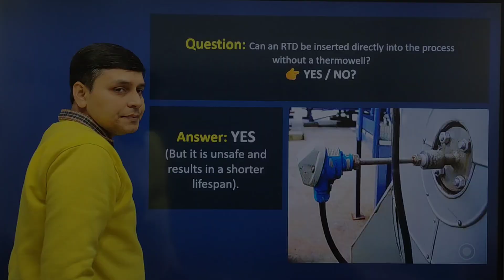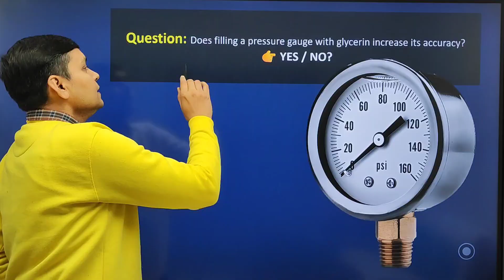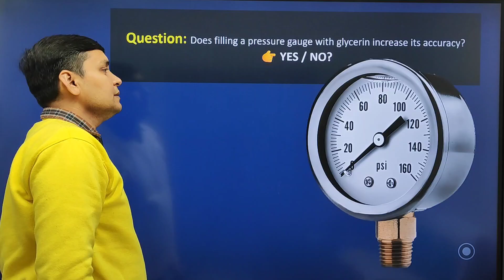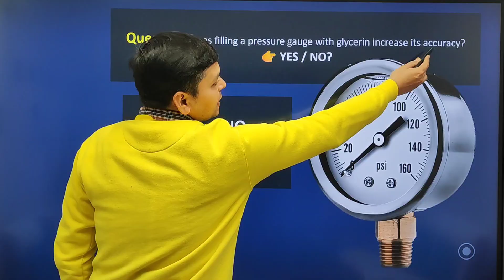The next very important question is about the pressure gauge. You must have seen that some pressure gauges are filled with liquid. This liquid is known as glycerin. So the question is, does filling a pressure gauge with glycerin increase its accuracy? And the answer is no. Filling the pressure gauge with glycerin does not increase the accuracy, but it is used for vibration damping.